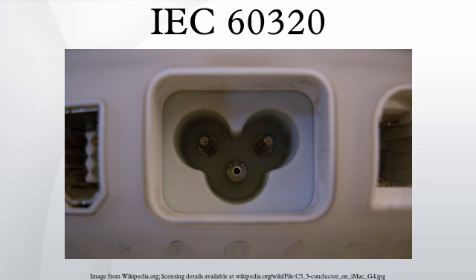The pin temperature is determined by the design of the appliance and its interior temperature, rather than by its ambient temperature. Typical applications with increased pin temperatures include appliances with heating coils such as ovens or electric grills. It is generally possible to use a connector with a higher rated temperature with a lower rated appliance inlet, but the keying feature of the inlet prevents use of a connector with a lower temperature rating.